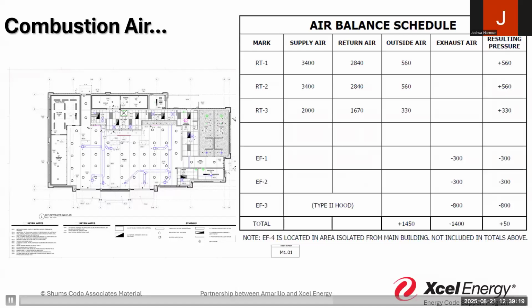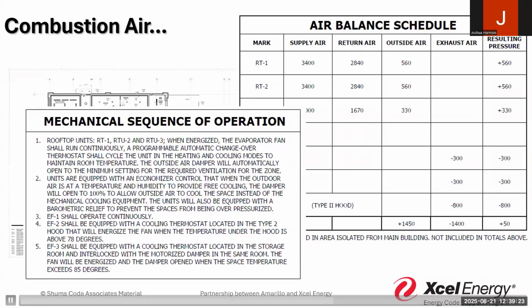We talked about whole house mechanical last week. What I'm doing is looking at those sequences, those controls, to say how it all works together. How does it balance so that I don't have unfettered or continuous exhaust fans operating continuously, drawing out the heat loss, so that I now have to bring in more tempered air and spend more energy to maintain the existing temperatures.